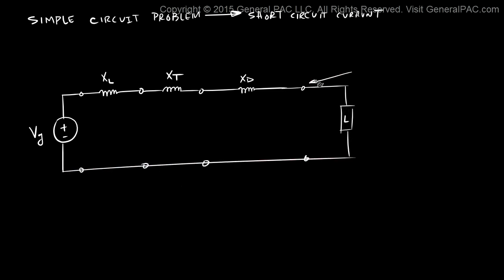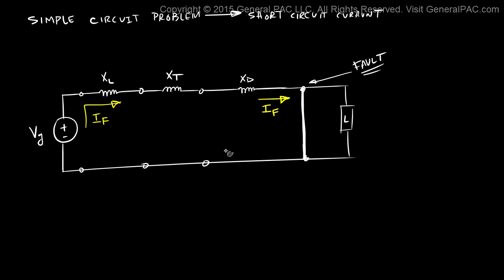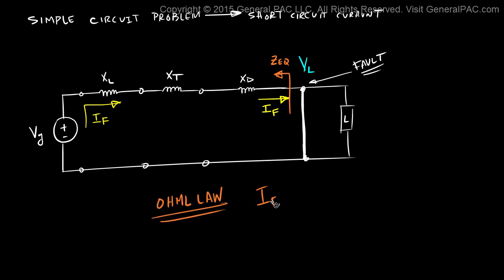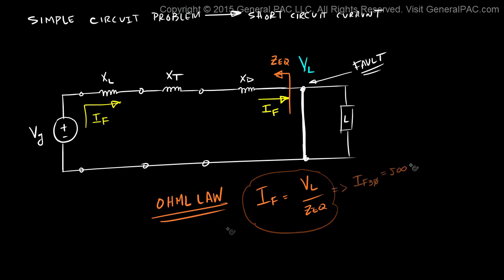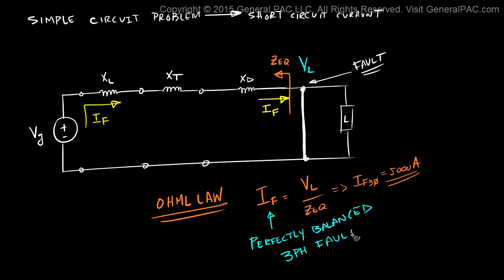Now if we had a fault at the terminal of our load — a short circuit — we should expect a huge short circuit current that comes from our generator and feeds our fault. To calculate this current, we take the voltage at the terminal of our load and divide by the equivalent impedance seen at the point of the fault. This is Ohm's law, plain and simple: current equals voltage over impedance. Suppose we get 5,000 amps of three-phase fault current. But we have simply calculated a perfectly balanced three-phase fault. How do we calculate an unbalanced fault, such as a line-to-ground, two-line-to-ground, or line-to-line fault with the same methodology?